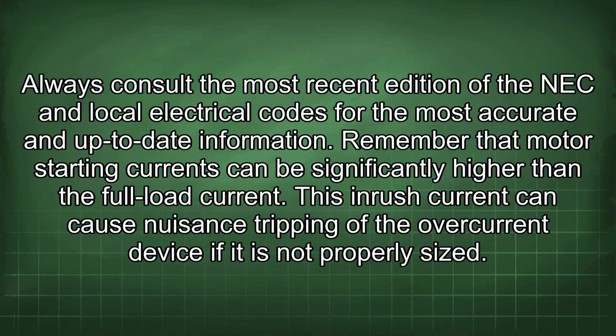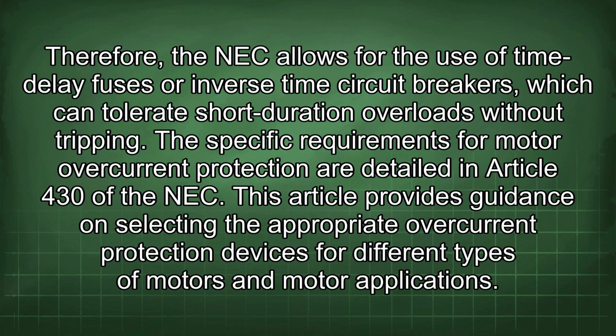Remember that motor starting currents can be significantly higher than the full load current. This inrush current can cause nuisance tripping of the overcurrent device if it is not properly sized. Therefore, the NEC allows for the use of time delay fuses or inverse time circuit breakers, which can tolerate short duration overloads without tripping. The specific requirements for motor overcurrent protection are detailed in Article 430 of the NEC. This article provides guidance on selecting the appropriate overcurrent protection devices for different types of motors and motor applications.